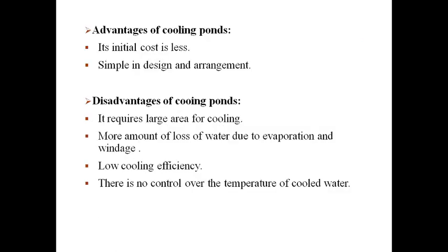Advantages and limitations of cooling ponds. Advantages of cooling ponds: initial cost is less, simple design and arrangement. Disadvantages of cooling ponds: it requires a large area for cooling, more loss of water due to evaporation and windage. Windage is nothing but drift losses. Low cooling efficiency compared with a cooling tower.